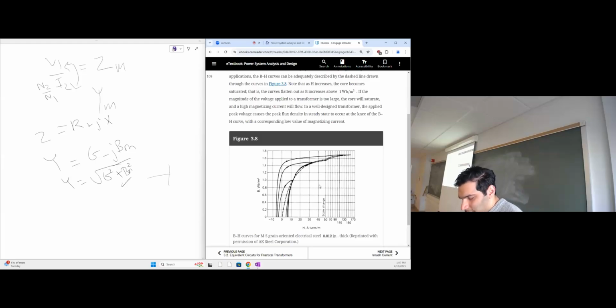The other good observation is that after reaching maybe 10 ampere-turns per meter of that intensity, we're getting a little bit flat, around 1.6 Webers per meter squared, which means that your magnet reached its full or almost full capability of generating flux. So there's no point in extending your intensity to 170 or so, because you'll still be around 1.6, okay? So based on this curve, reaching 10 is enough, if I'd like to energize the transformer. After that, there's no need for all that extension, because that would require a lot of intensity, while effectively we are getting almost the same flux. It's not worth it. Okay.